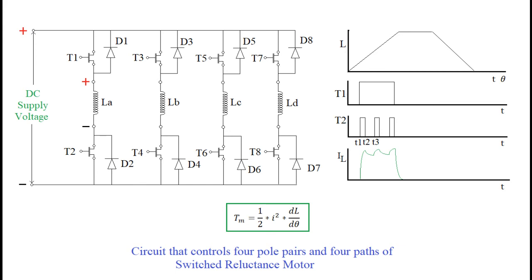Depending upon these rising values, we have to turn off one of the transistors for some period of time. During this period, energy is partly consumed to keep current value above certain value to keep sufficient torque available. For keeping approximately constant torque, we have to turn on and off the supply a couple of times. When rotor rotates up to a region of constant inductance, we have to turn off both transistors for all energy to return to the supply.